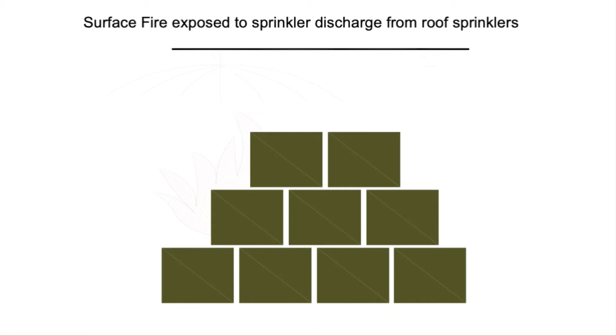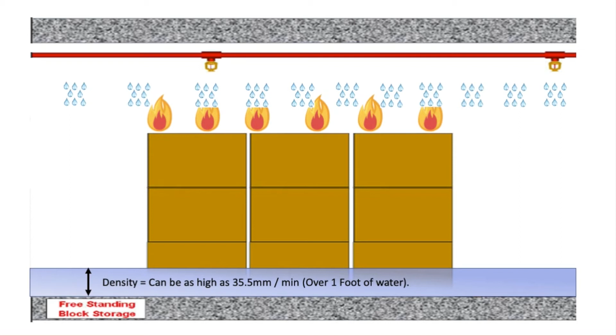So the depth of the water on the floor is called the density. That's measured in millimetres. So every minute you will get an amount of water. It could be 5 millimetres per minute, 10, 15, 20 millimetres per minute. I've done one up to 35.5 millimetres per minute. If you can picture it this way, over a design area, you would have over a foot of water in 1 minute. Now, if you think about it, warehouse sprinklers are set to run for 90 minutes. So 35 millimetres a minute could be up to 1 million litres of water over the period of 90 minutes, discharged over that floor area. So it's quite a lot of water. Hopefully you can understand the amount of water required in warehouse design.